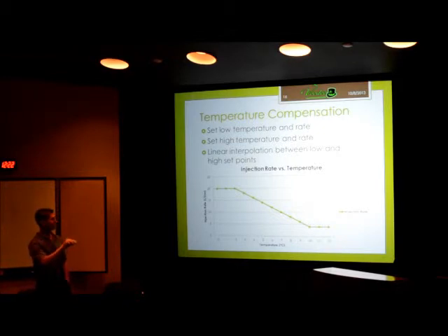So right here, anything below 2 degrees, full rate of the pump set. Anything above 10 degrees, it goes to its trim back rate, and it automatically reduces or increases in that span to compensate for temperature. Good example of this, I was doing some testing in our lab in Sundre there.